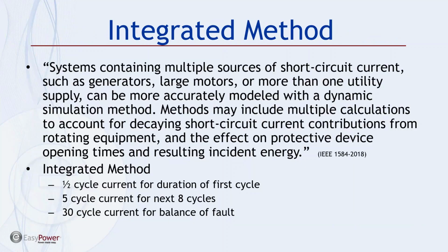Now, we've talked about the integrated method before, especially when we were talking about extended trip times and multiple complex systems that had multiple sources. And the question came up, well, if the integrated method as EasyPower implements it is a better, more accurate calculation method, why don't we use it all the time? And the justification was it wasn't part of the standard.